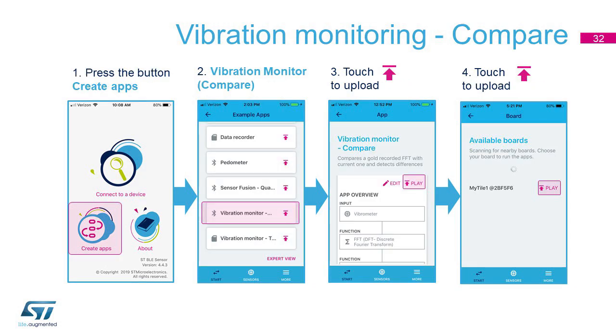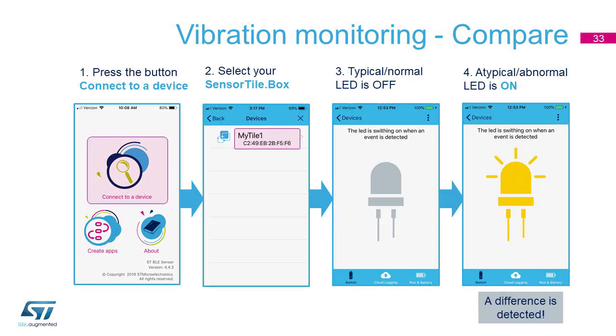After the first step has been completed, the second step can be run. This is called Vibration Monitor Compare, and is available in the Create App screen like the other examples. Upload it on SensorTile.Box when a machine verification test is needed. Position the SensorTile.Box on the machine exactly in the same position as during the first step. This second run will acquire the machine vibrations and compare them with what was recorded during the first step. If differences are detected, this usually means the machine has some new vibration modes, which can be generated by defective or malfunctioning gears or parts. A deep machine evaluation is then recommended.